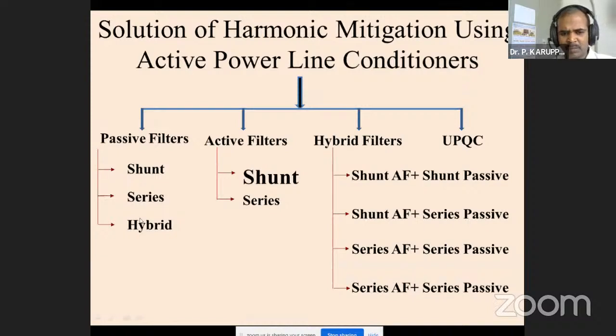Second, we have the active filter, shunt or series connection. Shunt filter is mostly suitable for current harmonic compensation, while series filter is mostly suitable for voltage harmonic problems.